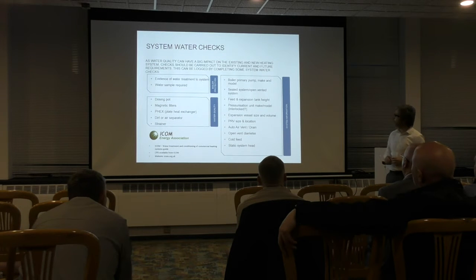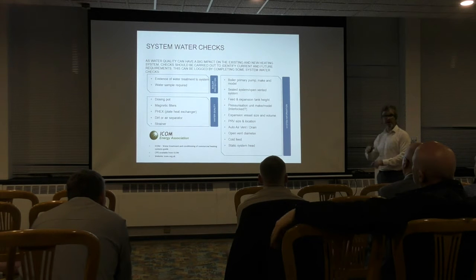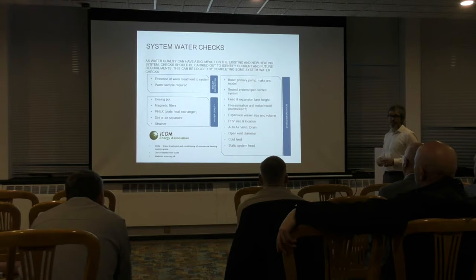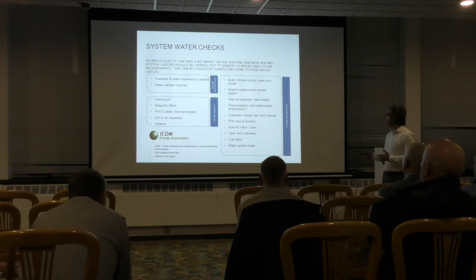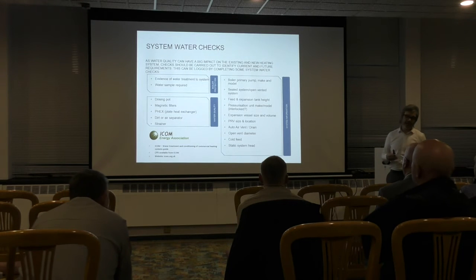But if it is an open vented system, you could have a big expansion tank. So what's the height of the tank? Because that will obviously then determine the pressure you're getting at the boiler. If it's a sealed system, we'll have a pressurisation unit. So again, what's the make and model of that? Because that can help if you are looking at replacing that.